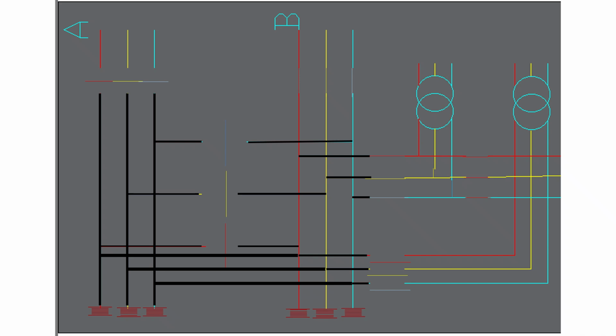Now the transformer capacity is too high, so in the railway system we feed one side with one transformer and another side with another transformer. In between the two transformers the overhead system is insulated, so that bridging is not possible because there is a phase difference in the Scott connection and also in the open delta connection. But this is the basic system I have shown to change over the power. Later I will show you how in the Scott connection and in open delta connection we change over the power supply.